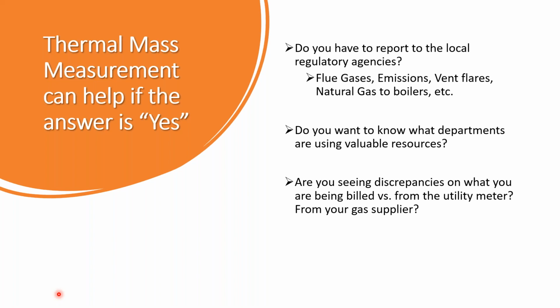If you can live with 1% accuracy across your flow scale, and are willing to save a little bit of money, because typically a 1-inch inline Coriolis unit might be $5,500 to $6,000, whereas a thermal mass unit might be $3,000 or $3,500, depending on the application. So you've got to do that justification. We've had customers in the past who have switched from Coriolis to thermal mass technology because they said we can live with 1% and save a couple thousand dollars per unit. Coriolis is a very good technology, but you just have to know that the cost of that technology is also something you're going to have to contend with.